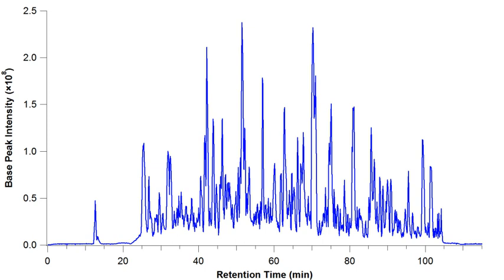The size of the mass tolerance window typically depends on the mass accuracy and mass resolution of the instrument collecting the data. This is useful for re-examining data to detect previously unsuspected analytes, to highlight potential isomers, resolve suspected coeluting substances, or to provide clean chromatograms of compounds of interest.